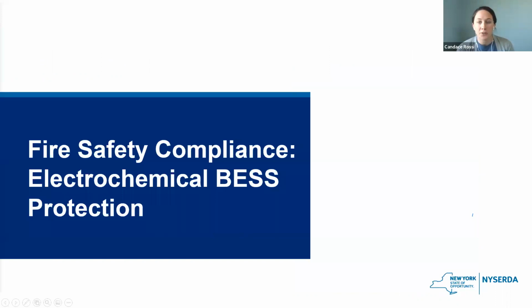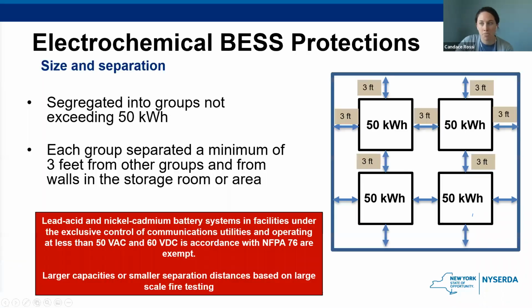So we just went through all the general installation requirements that all systems within the scope must meet unless there's a specific exemption listed in the code. And now we'll begin the electrochemical storage system protection requirements. So first one we have here is the size and separation. And if you can remember back to our little circle chart regarding thermal runaway, this is one of the first preventive measures that are put in place to try to avoid propagation.